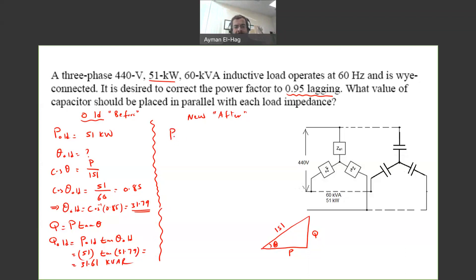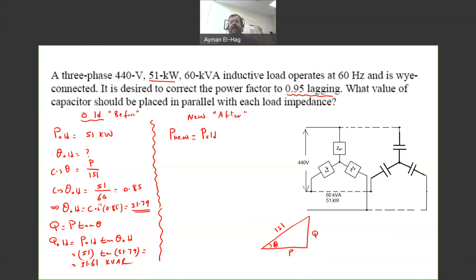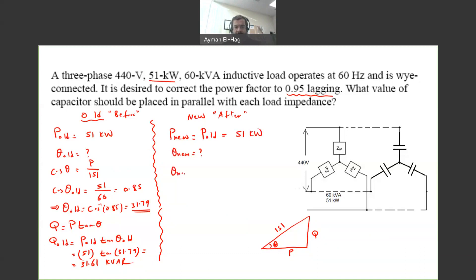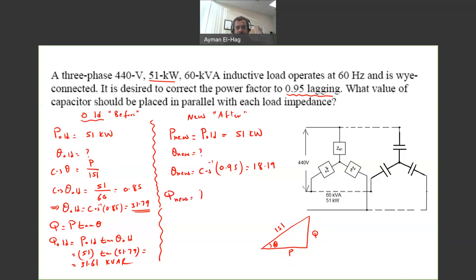Now let's move to the new values after connecting the capacitor bank. P_new is not given explicitly, but when we connect the capacitor bank we are supplying reactive power only — we are not affecting the active power. So P_new always equals P_old = 51 kW. For theta_new, we use the desired power factor: theta_new = cos⁻¹(0.95) = 18.19°.